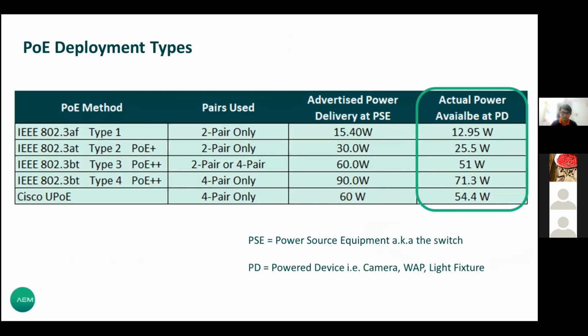Okay, a little bit of IEEE spec when we look at this so-called wattage. The last column is what we're talking about, the real power—at the end of the cable, you measure the power output. This is the minimum you should get based on the IEEE standard. For 90 watts, you should get a minimum of 71.3 wattage. Anything less than that is considered non-compliant, considered a failure.